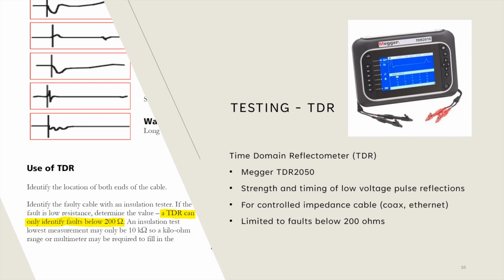But we didn't end up finding anything mid-span. So upon looking further into this, the TDR is not really the right tool for a multi-stranded cable, or at least it's not designed for that. It's designed for a controlled impedance cable, like a coax or an Ethernet cable. And the user manual actually says that a TDR, or at least this specific model, can only identify faults below 200 ohms. That's quite low. So we were way above that with our 10 kilo ohm fault.